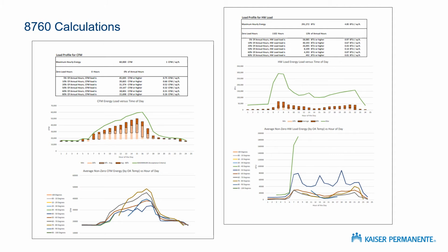But if you look at that example on the right there, that's not a mistake. The difference between the peak heating and the 80% heating requirement is a 600-to-1 turn down. That's what the plant needs to be capable of. That's what the pumping system needs to be capable of. Most of our systems run really, really inefficiently, not because we're selecting inefficient equipment, but because our system design just simply doesn't accommodate the most common operating conditions. And we want our systems to be radically energy efficient at the most common operating conditions.